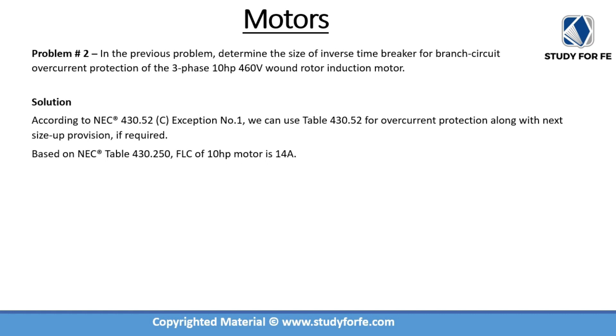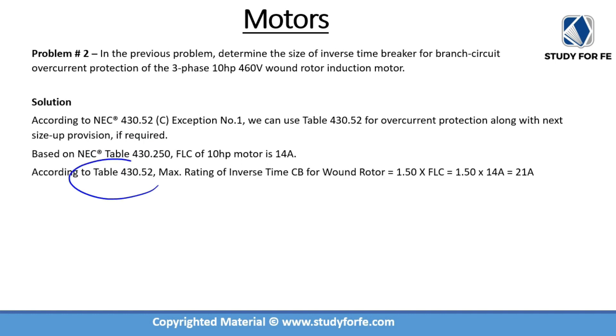In problem number 1, we already calculated the FLC of the 10 horsepower motor as 14 amps using table 430.250. Coming back to table 430.52, the maximum rating of an inverse time circuit breaker for a wound rotor application is 150% of FLC — that is 1.50 times 14 amps — which gives us 21 amps.